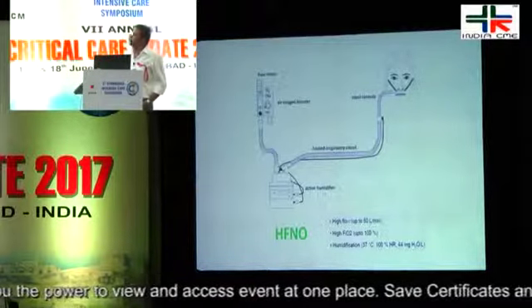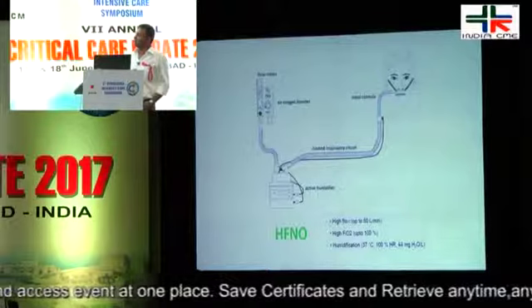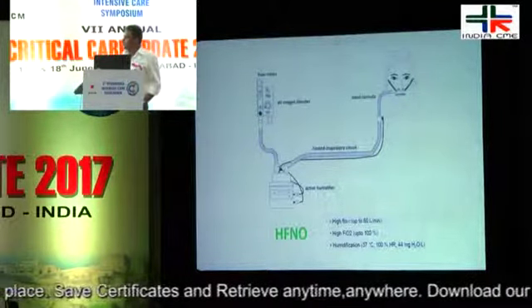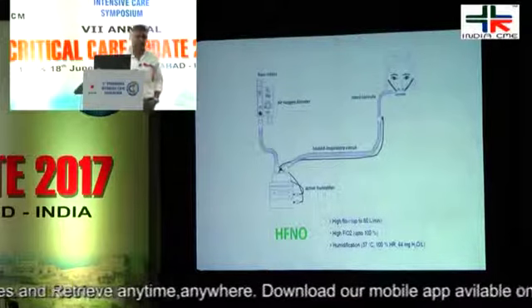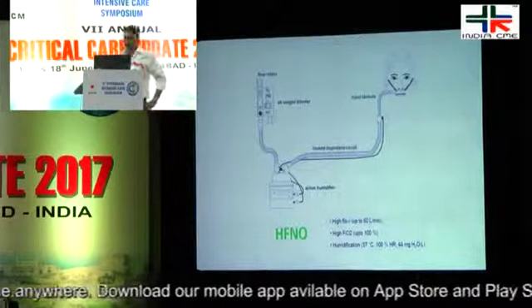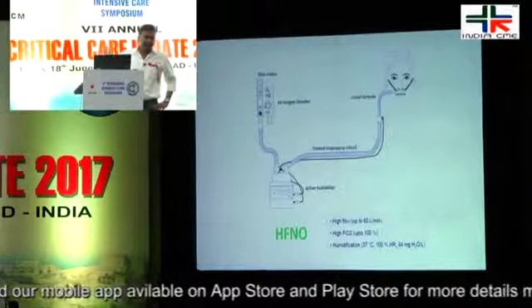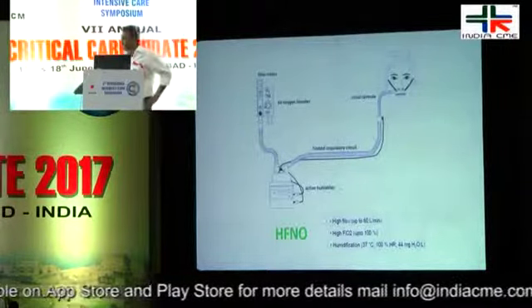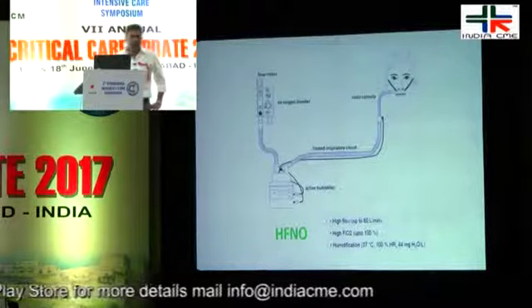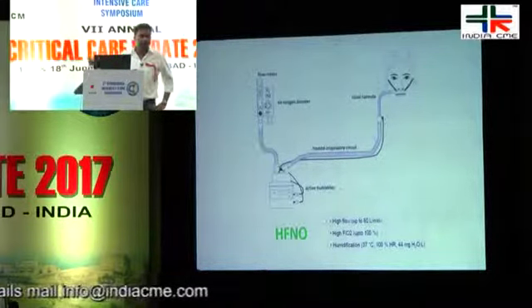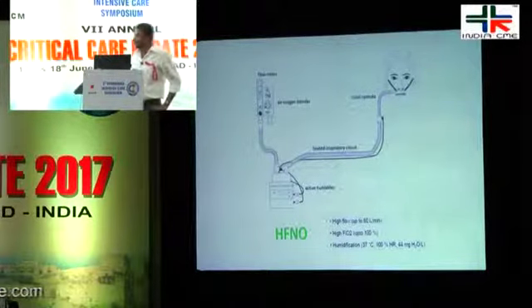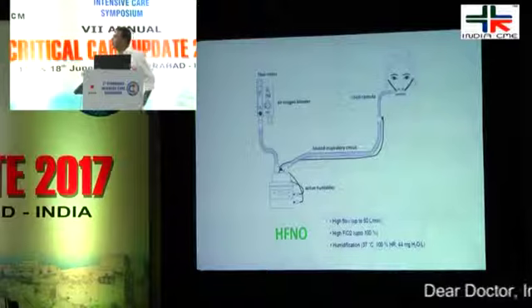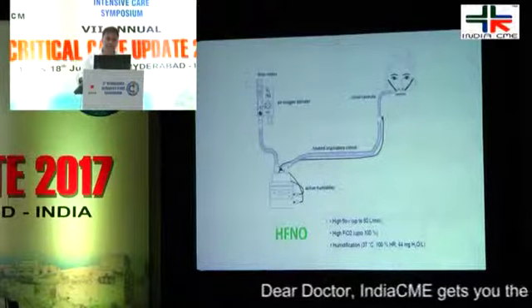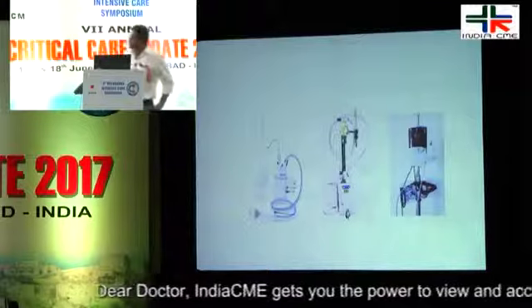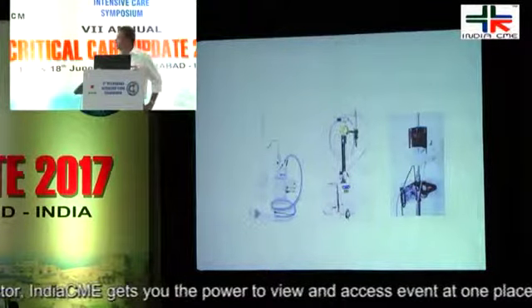So, its composition is pretty simple. You have an air oxygen blender with an oxygen source, and you need to give up to 60 liters per minute, so the source has to be dependable. Then you have a flow meter which, unlike our regular flow meter, is on a higher scale from 0 to 60. Then you have an active humidifier, which will humidify as well as regulate the temperature of the oxygen delivered. Then you have a heated inspiratory circuit and a standard nasal cannula which looks a little different. There are different models available, but in India right now only one model is available, and it is easily available, not that different.